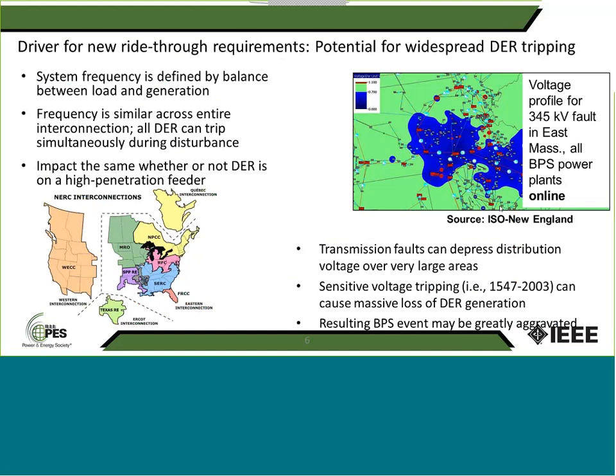ISO New England did a study in their territory. What they did, they put a fault on a 345 kV line, and they showed us that the voltage goes below 70% in this particular example, the light blue areas, and even less than 50%, the dark blue areas. That's basically what they're showing, that in a very large area we will experience a momentary undervoltage, and they're really concerned that with the high penetration of solar, especially in Massachusetts and other states in New England, we're going to lose a large portion of DER on the distribution system.